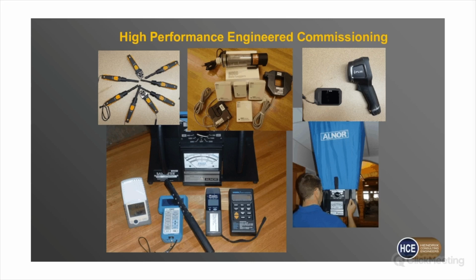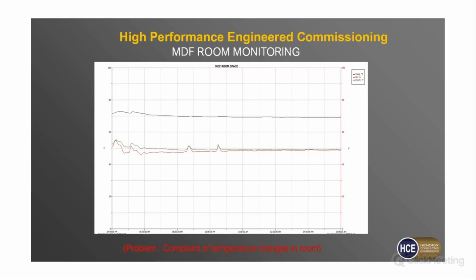A lot of times you may wonder, why are we going to do that? Well, if you've got a technology guy complaining that his servers are too hot because the air conditioning in the IDF room's not good, but you've got dedicated AC in there, we put a data log in there and let it run for a week, and you can show him that you maintained 65, 70 degrees 24 hours a day for a week. All of a sudden those complaints magically go away when you can show them some data.